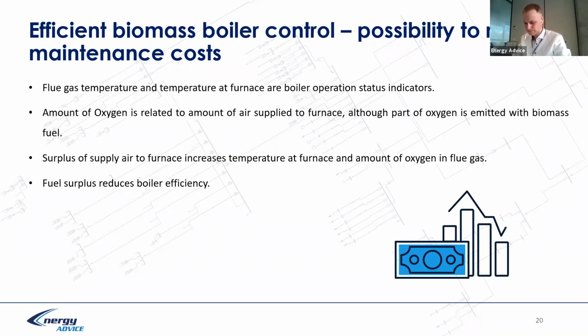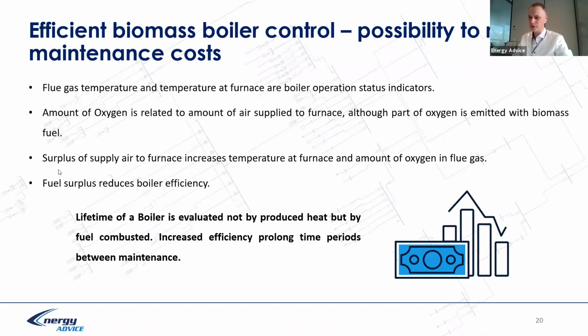So what we see in the boiler dynamic, if we push more fuel at that time, when it is required, we need to burn this fuel, and this makes the impact on the reduced efficiency. And what does it mean? Efficiency is division of two numbers. One number, it's like a KPI. It's produced heat divided by burned fuel in megawatt hour or calories, for example, or joules. So if we burn surplus fuel, in fact, this would decrease our lifetime in general. And lifetime is evaluated by produced heat and combusted fuel, increased efficiency, prolonged time period between maintenance. It's general rule.